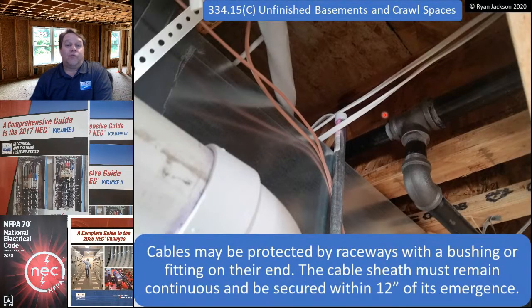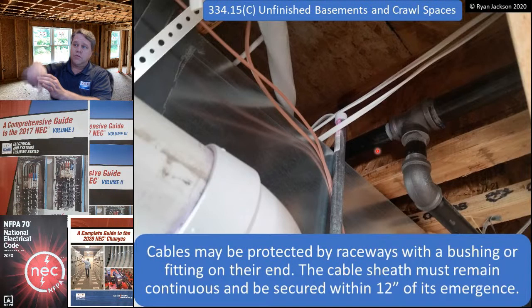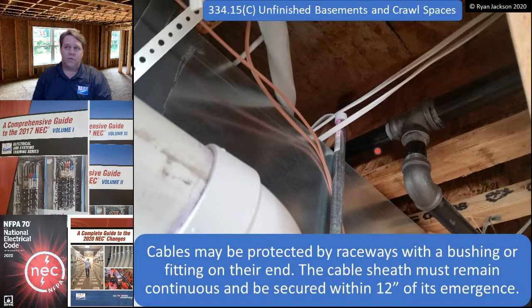Cables may be protected by raceways that have a bushing on their end. Interesting that this is only for unfinished basements and crawl spaces. You'd think it would be anywhere. But cables can be protected by raceways that have a bushing or a fitting on their end. The cable sheath must remain continuous all the way through the raceway and be secured within 12 inches of where it comes out of the raceway. So you can't strip the cable and push it through here. You can't change wiring methods. You didn't change from NM cable to EMT. This is just some physical protection. You still have to follow the rules for NM cable. So push that cable down through there, put a fitting, secure it within 12 inches, good to go.